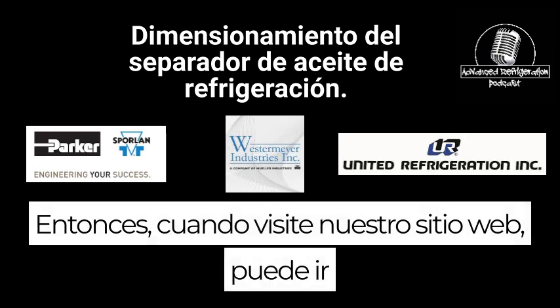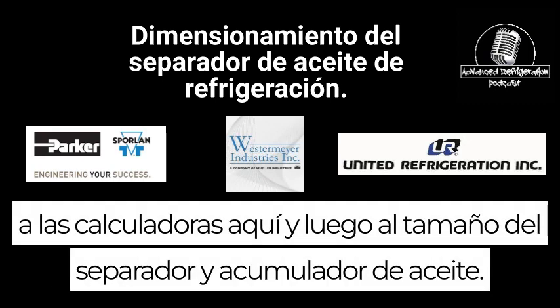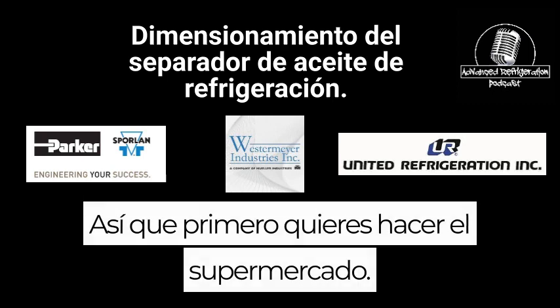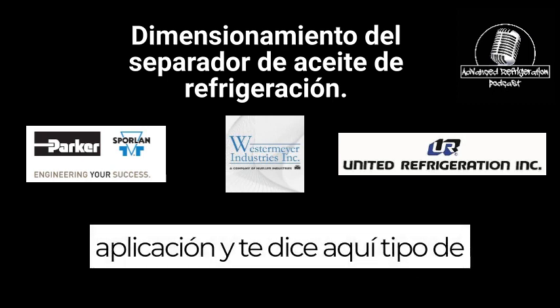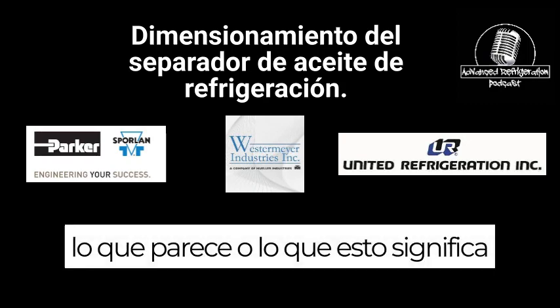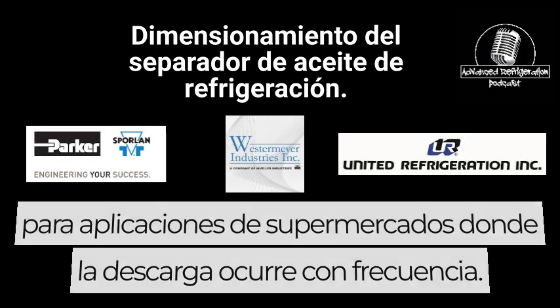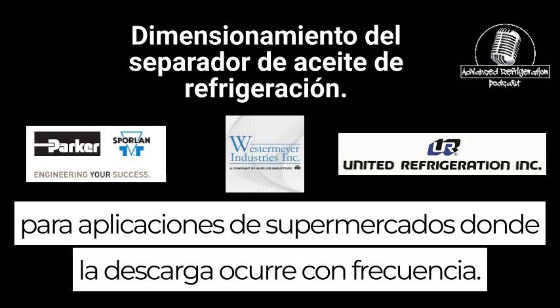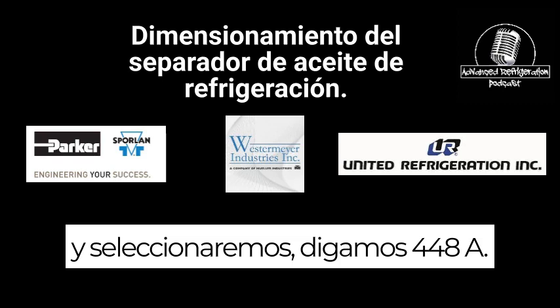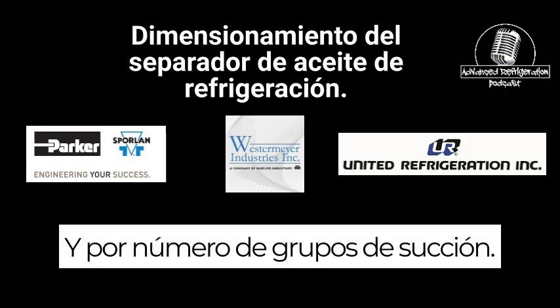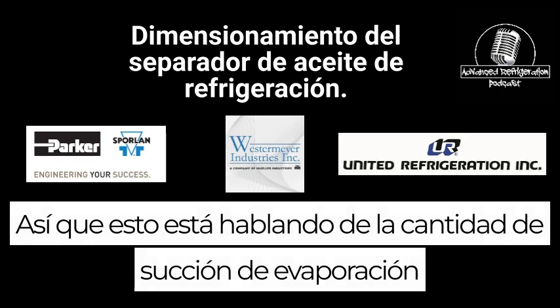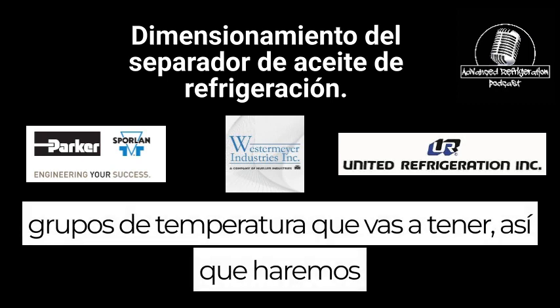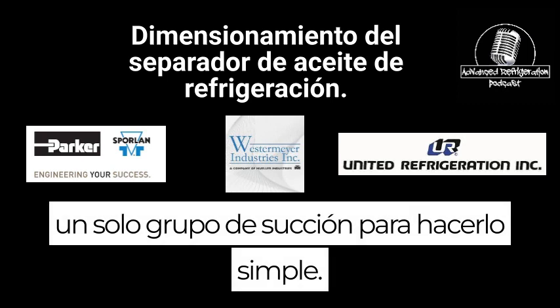So when you go to our website, you can go to calculators here, and then oil separator and accumulator sizing. First you want to do the supermarket application, and it tells you here what this means for supermarket applications where unloading occurs often. Then we'll select, let's say, R-448A, and for number of suction groups, this is the number of evaporating suction temperature groups you're going to have. We'll do a single suction group to make it simple.